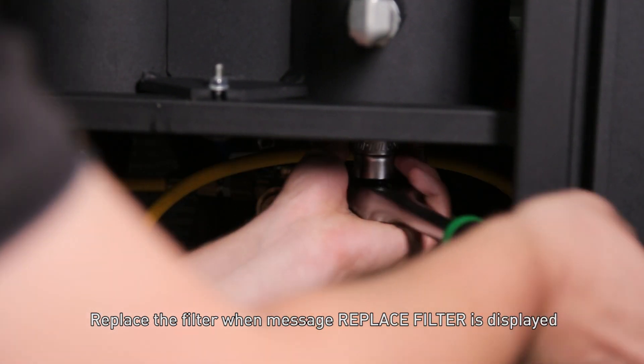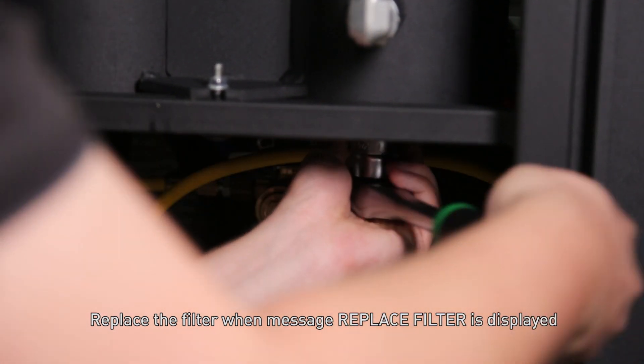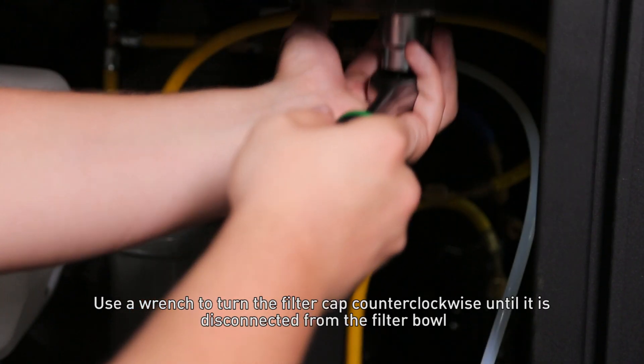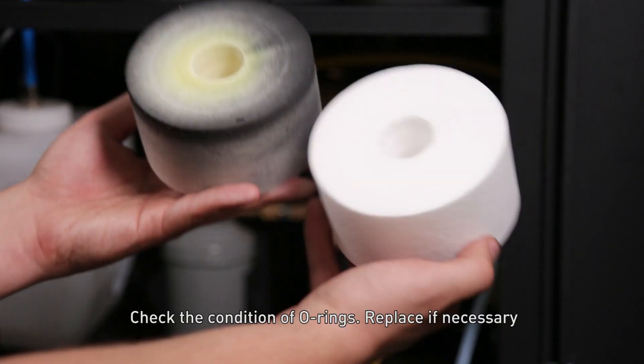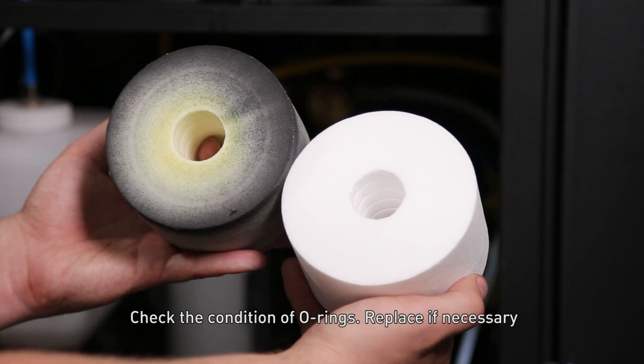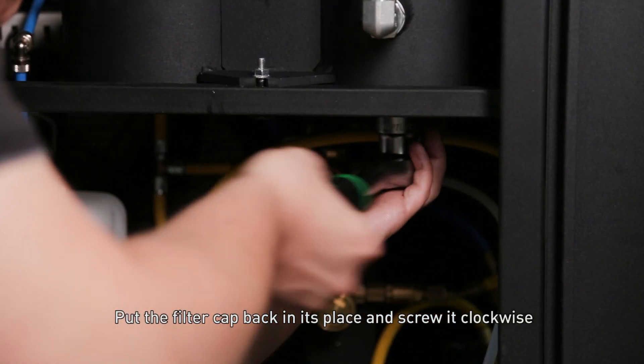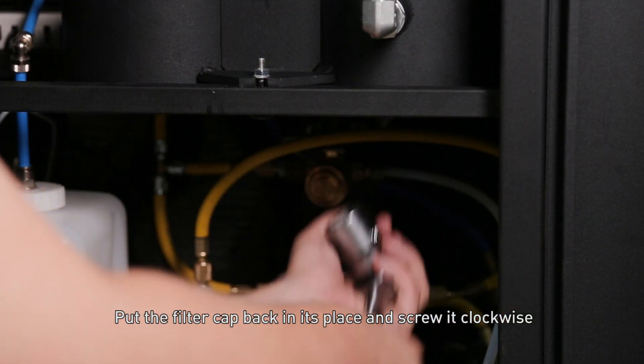Replace the filter when the message 'Replace Filter' is displayed. Use a wrench to turn the filter cap counterclockwise until it is disconnected from the filter bowl. Check the condition of the O-rings and replace if necessary. Replace the filter element, then put the filter cap back in its place and screw it clockwise.